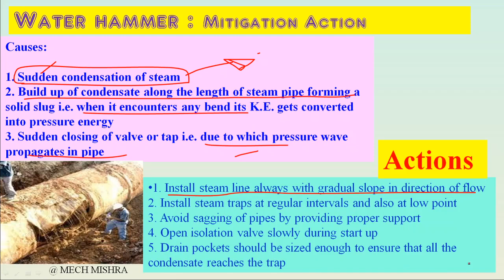So what are the mitigation actions which we can take to avoid such things? First is install steam lines always with a gradual slope in the direction of the flow, so that it will not form the slug. Install the steam traps at regular intervals and also at the low points. So that's very important. And third is avoid sagging of the pipe by providing proper support. This will also form slug.